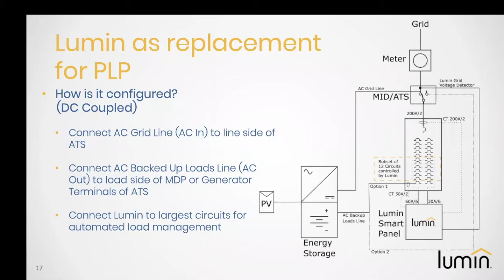Equally important, we're going to go into a bit of detail about common barriers and maybe when we're not the best fit. First, one of the most common barriers is really a geographically specific one, and it pertains to getting that ATS or that MID installed between the meter and the main. We know with California and their all-in-one meter and load center combos, this can be particularly difficult. Most often we see installers having to add an additional load center and either relocating all of those circuits to this new service from that existing all-in-one, and then using Lumin to manage the heavy loads, or even just leaving those heavy loads upstream in the existing load center.